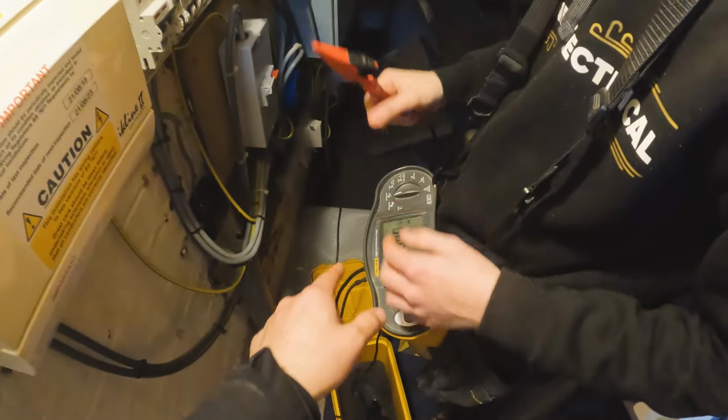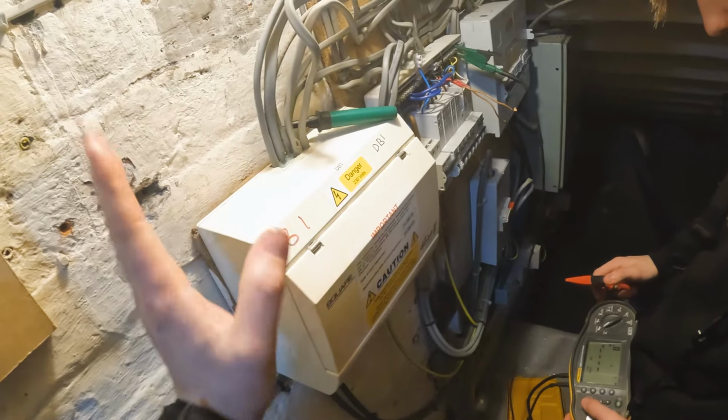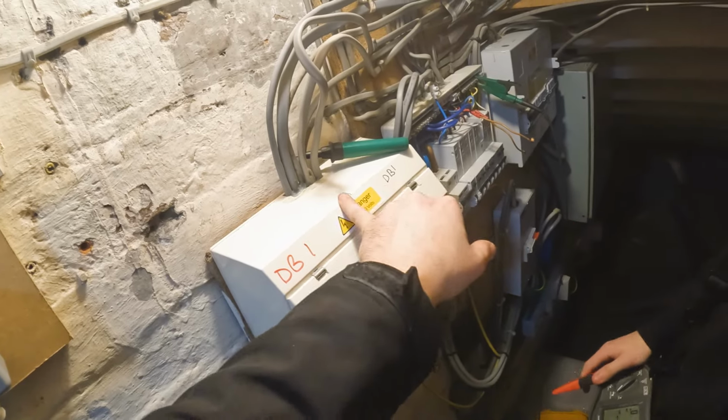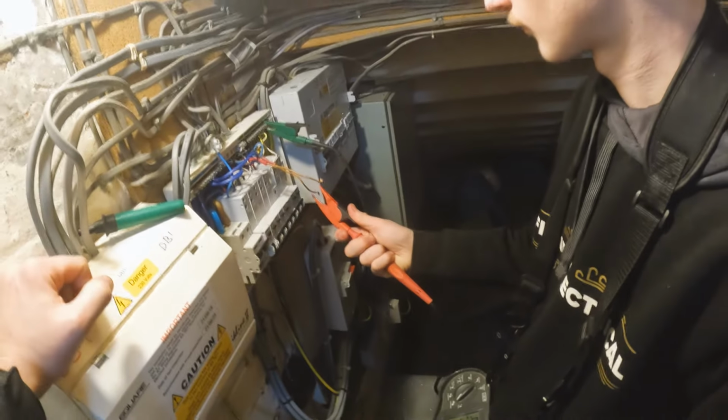Right now, we're going to test it at the bigger scale, so we've gone from 0 to greater than 2,000, and now we're jumping up the scale. If this is low resistance, that's high resistance. So we're testing from 0.01 megohm all the way up to greater than 200, if we test at 250 volts. So let's do line to earth on that one.